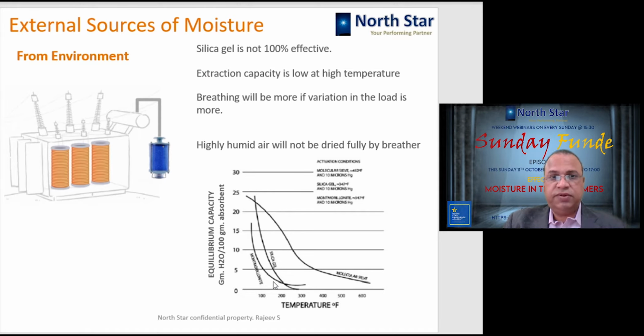Take the external sources. As we have discussed, silica gel is not 100% effective, and its capacity greatly depends upon the temperature. Look at this graph, which shows the amount of water that 100 grams of absorbent can take. There are other absorbents also, but we are referring to silica gel. Unfortunately, this graph shows temperature in Fahrenheit. If the temperature is somewhere around 110 Fahrenheit, the gel can absorb around 24 grams of water per 100 grams of gel. As the temperature goes up, this capacity is drastically reduced.